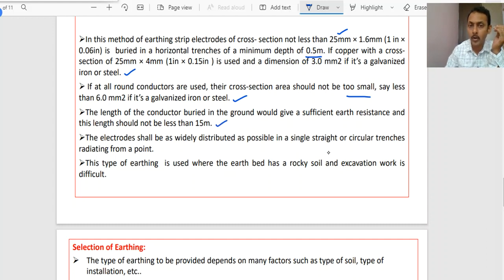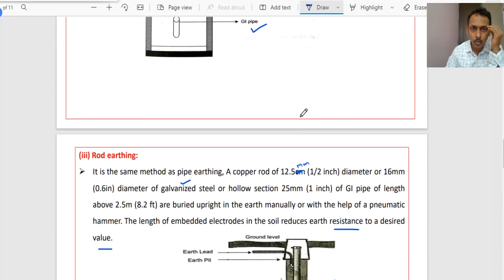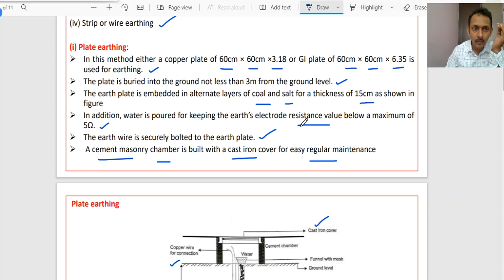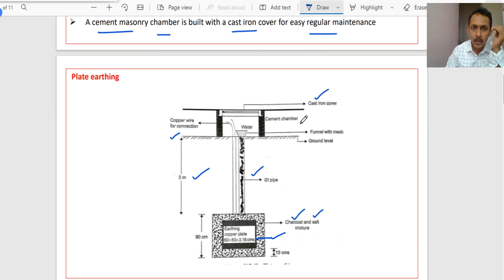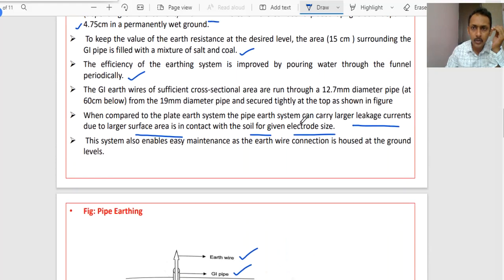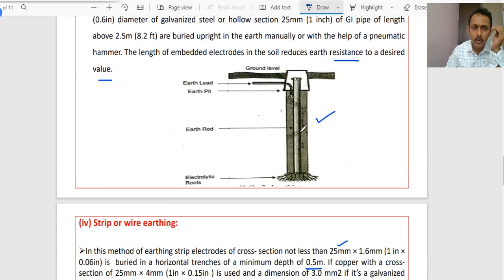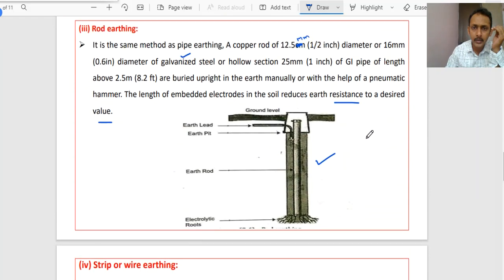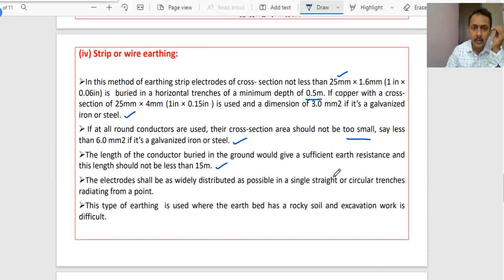Here you have to go for more depth. In the previous cases the depth was less. If you observe, for plate earthing you have gone to a depth of not less than 3 meters. But if you observe here, the depth is much more. In strip or wire earthing, you should go to a length of not less than 15 meters. Up to there the arrangement should be made, right?